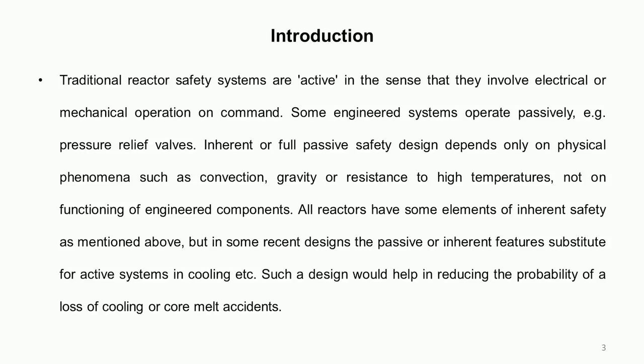When we say passive, the other one is active — as you have in English the active voice and the passive voice. Active means it involves either electrical or mechanical components which get actuated and then give command to a particular system. If you take a safety relief valve provided on many boilers, the moment the pressure rises beyond the setting, it opens — the pressure is sufficient to compress the spring and open. So this is a passive way of releasing the pressure.